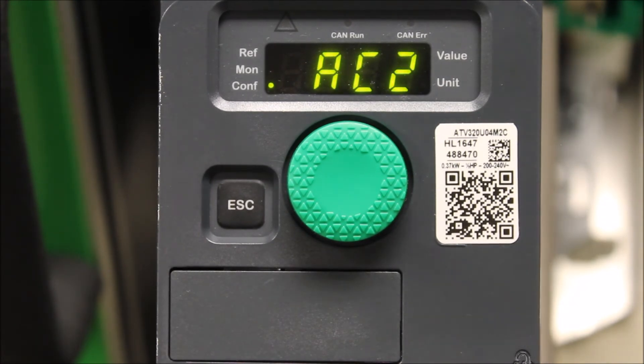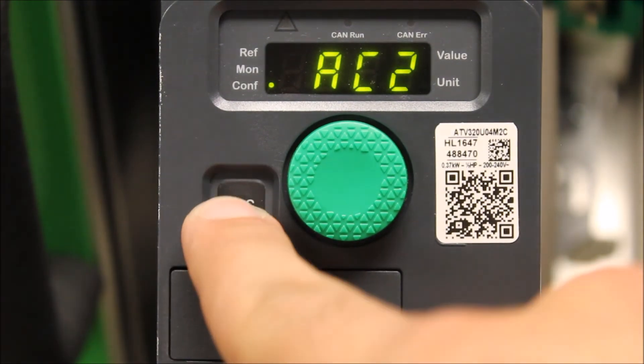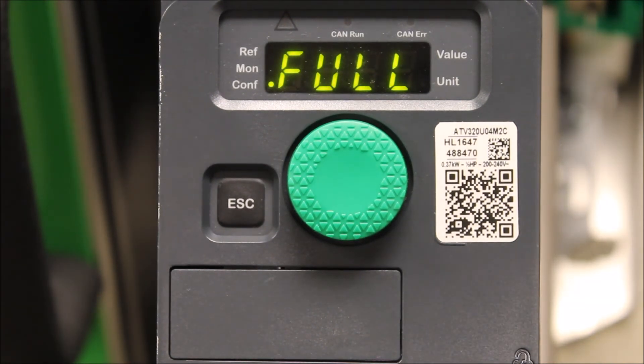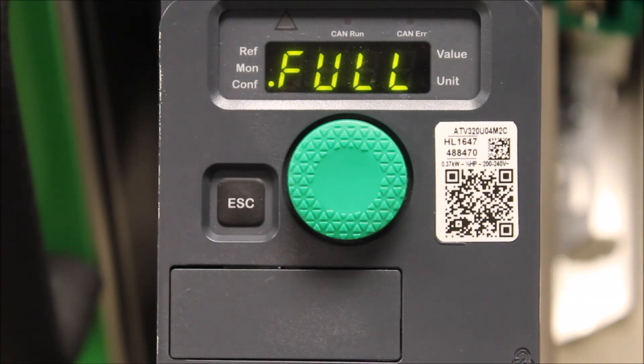So this is basically how you program the ATV 320 drive to do ramp switching - either by using a digital input or by using a frequency threshold to toggle the secondary ramp up and ramp down times.